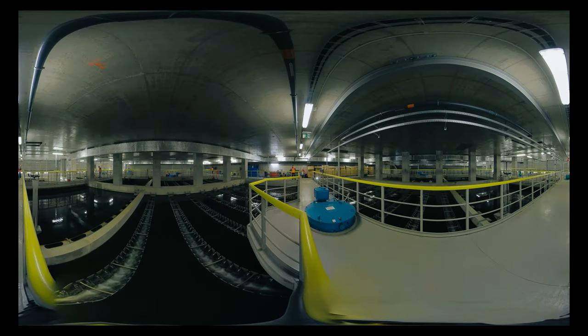Hello, here I am. At the previous stops we talked about bacteria, and they're powerful, but not all powerful. Even after biological treatment, substances remain in wastewater that would have a negative impact on the environment. The main one is phosphorus — if there's too much of it, it causes excessive growth of algae and cyanobacteria. For that reason, we reduce its content by precipitating it. At the very end, we then kill off any pathogens that could occasionally be present using ultraviolet radiation. And there ends the journey of wastewater through our treatment plant — in about 20 hours, it has been transformed from a murky soup into clean water that we can return to nature.